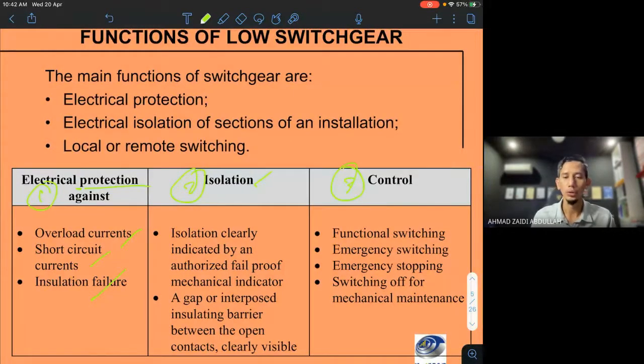So for switchgear, we need to design it so it is able to control the system lah. So let's say we want to perform maintenance, we can simply control the supply, we just switch off the protection part lah. Okay, switchgear tu kita off dekat switchgear, let's say for the SSB 1 kan, we switch off that, and then we can do maintenance there, alright, on the SSB 1 lah.